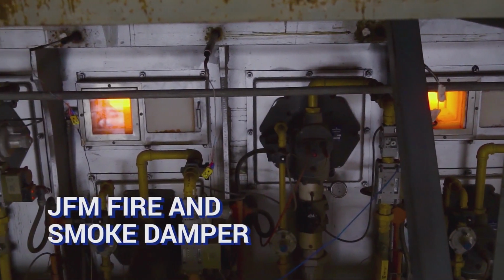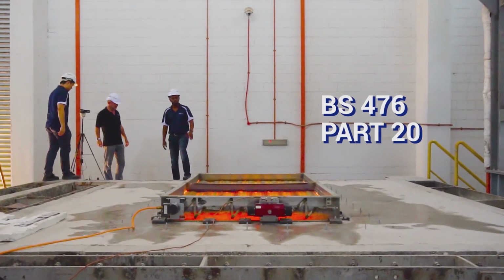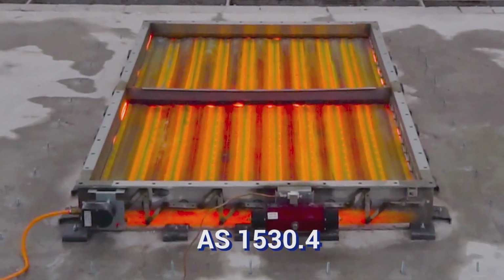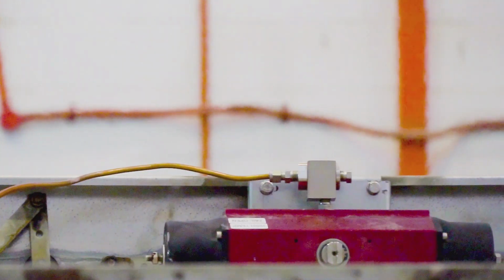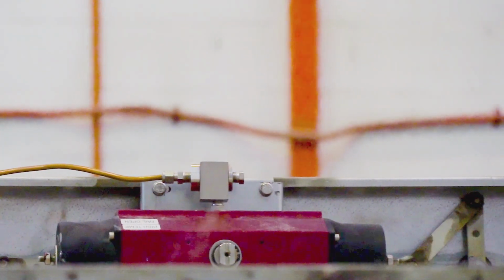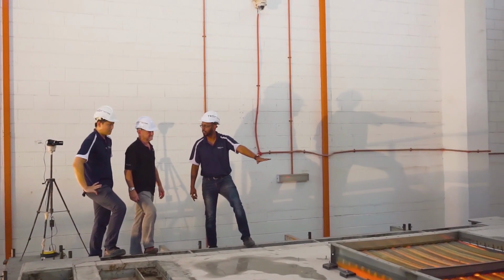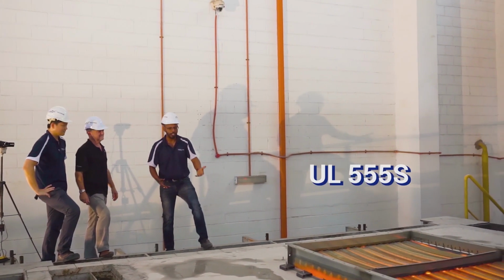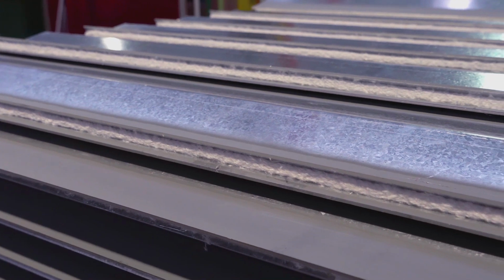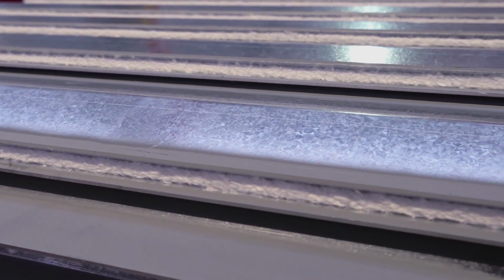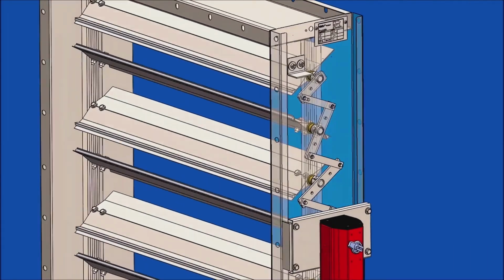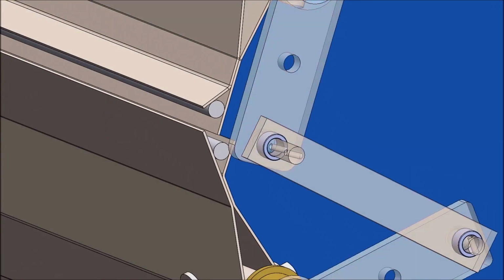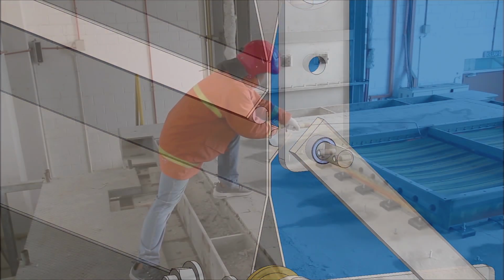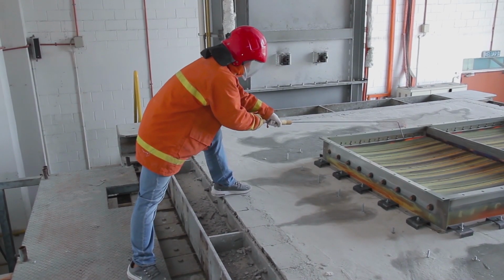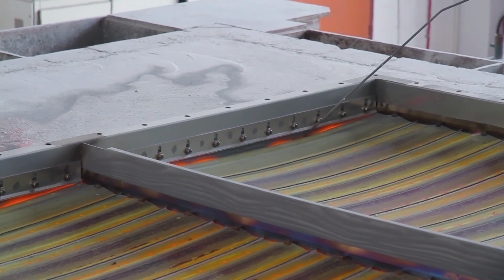The JFM fire and smoke damper has a 4-hour fire integrity rating in accordance with BS 476 Part 20 and AS 1530.4. In addition, the damper has a very low smoke leakage rate, which is almost half that is required to meet the Class 1 rating detailed in UL 555S. Each damper blade is of double-skin airfoil design and has a V-groove running along the entire length of both edges, which houses a compressible ceramic seal. This ensures that an impenetrable fire and smoke barrier is created when the damper closes.